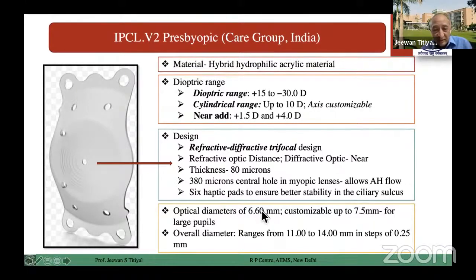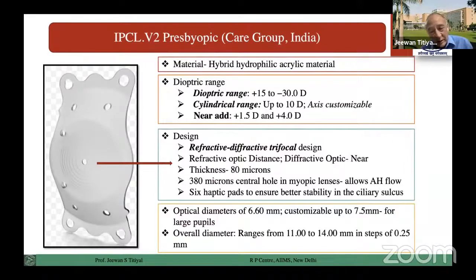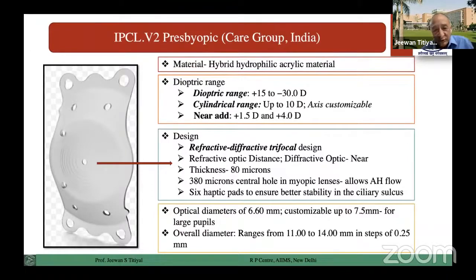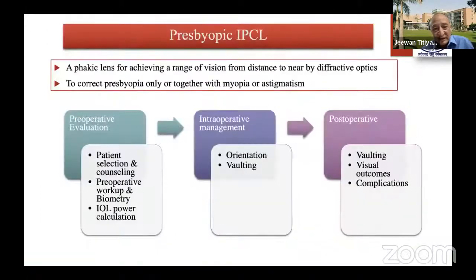At this age group, with the advantage of correction, the other visual phenomena are normally well tolerated by these lenses. Very thin lens in the center — 80 microns — and it also has a 380-micron center flow design, which may decrease the onset of cataract in these patients. Most importantly, the optic diameter is 6.6 millimeters, which can be customized to a larger diameter, especially for patients with larger pupil size. But in the Indian population, the pupil at this age group is not very large, so most patients will fit into these designs.